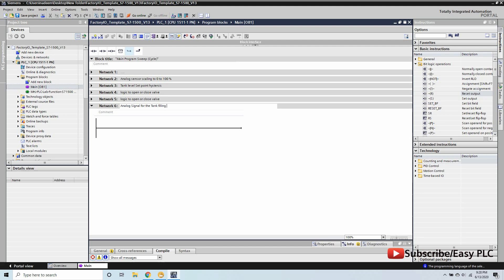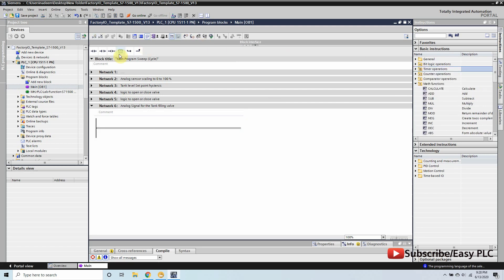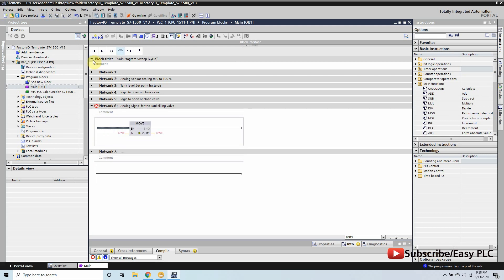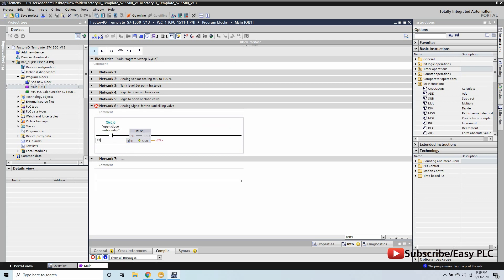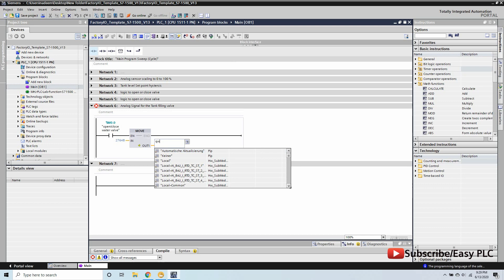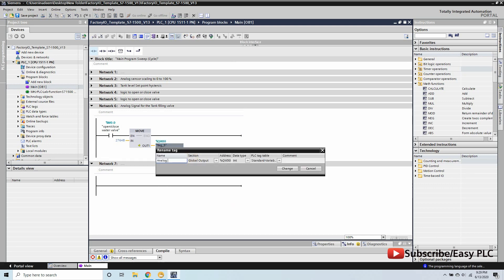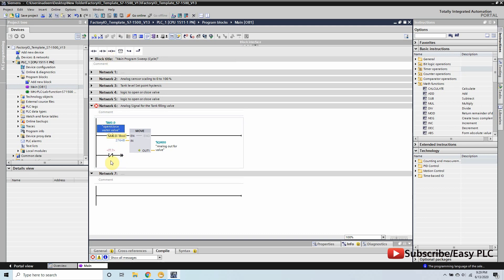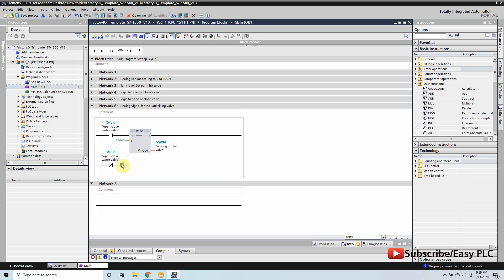In Network 6 we will make the logic to send the command to open and close the filling valve. Since our actuator has an analog input connected to our PLC at QW30 address, if memory bit M0.0 is on we will use a MOVE instruction to write 27648 to the QW30 address, which will fully open the filling valve. Similarly, when the tank level has reached the setpoint we write 0 to the QW30 address, which will fully close the filling valve.